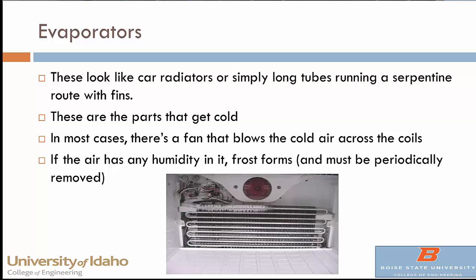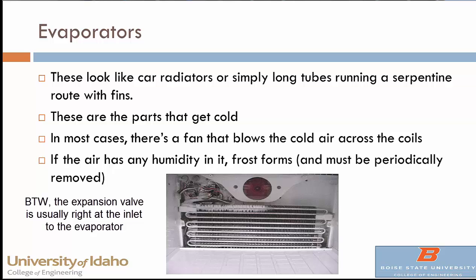Going downstream in the direction of refrigerant flow, you find evaporators — the cold part where heat is picked up. A typical example is the serpentine coil with fins in the back of a refrigerator: refrigerant enters as a liquid-vapor mixture, boils throughout the process, and exits as superheated vapor. There's often a fan to move air through. In food processing environments, where there's always humidity in the air, frost builds up on the cold coils and fins, limiting airflow and heat transfer and requiring periodic removal.